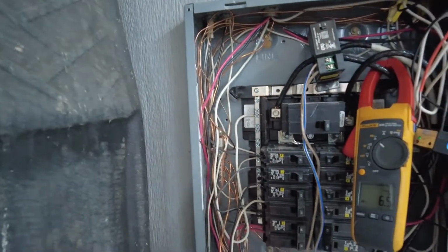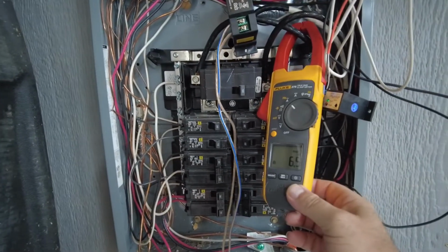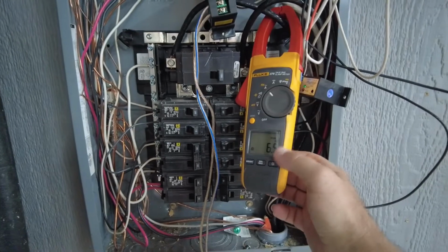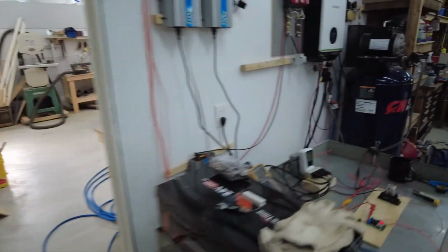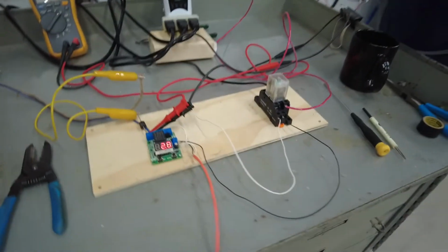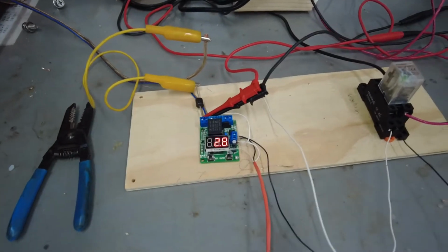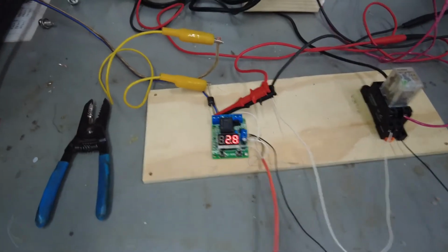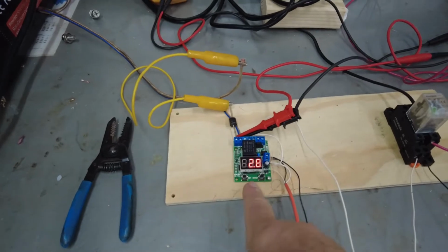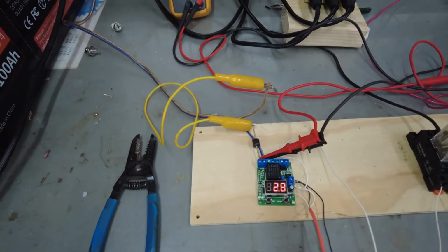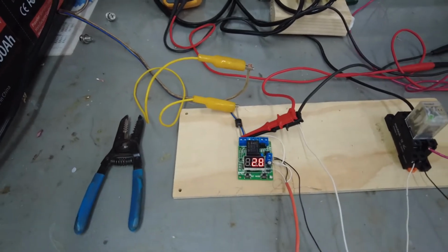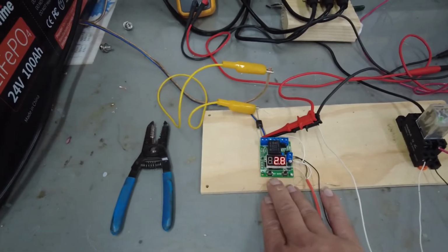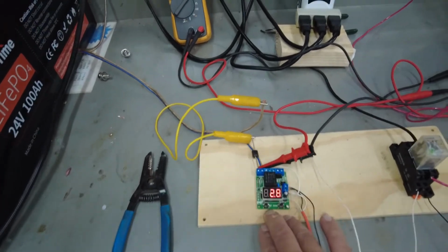Right now, you can see on the Fluke here, we're doing 6.5 amps. I have on just basically the shop lights. I don't have any solar going right now. And you can see that's at about 2.8 volts. Now it's not perfect. In a perfect world, that should be 3.1 volts on there. But like I say, that CT is not perfect. So that's showing the 6 amp draw.